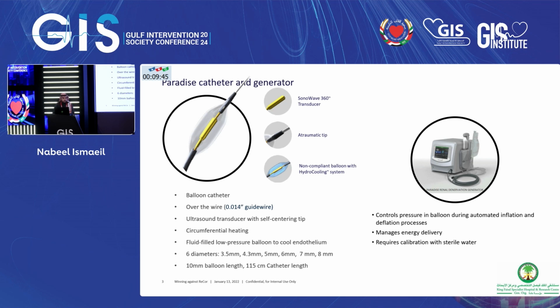So this balloon is over the wire compared to the rapid exchange catheter, and it is a 7 French guiding catheter compared to 6 French. Both are being used through a transfemoral approach. And for this one, we have available 6 diameters, starting from 3.5 millimeter balloon all the way to 8 millimeter balloon. And the balloon length is around 10 millimeter, and the catheter length is around 115 centimeter.